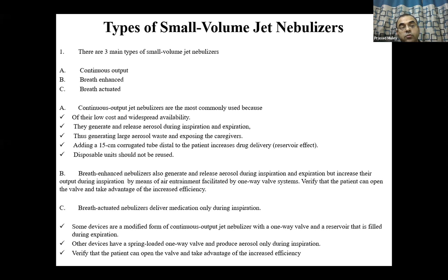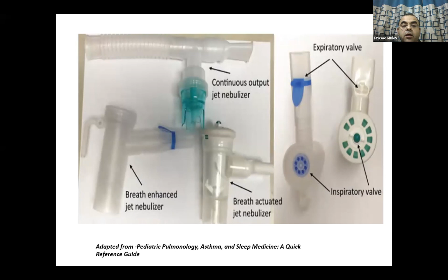So a lot of different types of devices are available, but the majority of even private practitioners and hospitals still use the continuous output. This is the continuous output which we use. That is breath enhanced, and this is breath actuated, in which nebulization is used only during inspiratory time. And here nebulization is given during both inspiration and expiration, but predominantly the valve system doesn't allow it during exhalation, only during inhalation.